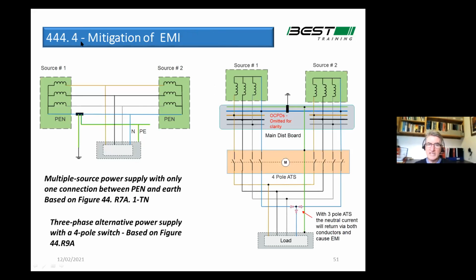So 444 deals with electromagnetic interference. It causes voltage disturbances and electromagnetic interference. And it gives lots of different diagrams and guidance, like the ones I've shown here. There's just 2 examples of things you should do to mitigate the risk of electromagnetic interference. The diagram on the left shows a dual-fed, double-ended substation arrangement, and shows you should only neutralize at 1 point. Obviously, if you neutralize at both points, your entire earthing system would be in parallel with the neutral conductor, and you would have leakage currents. You'd have neutral current returning through your earthing system. So that's why we don't do that.